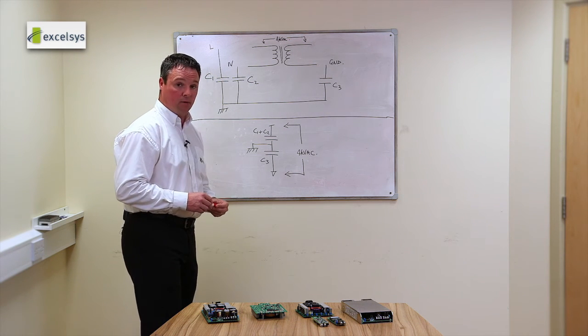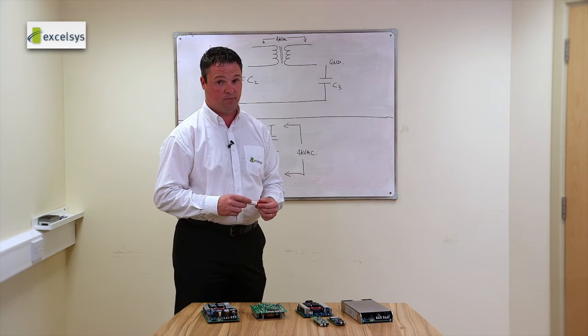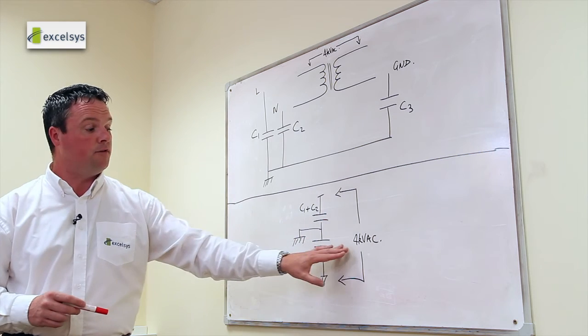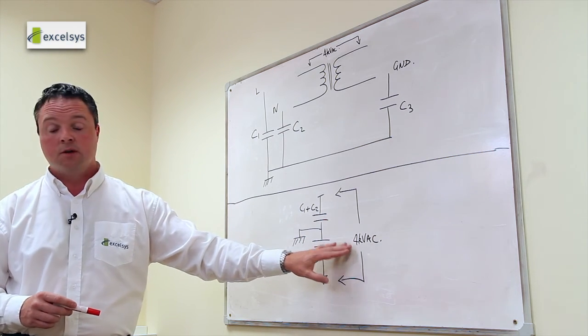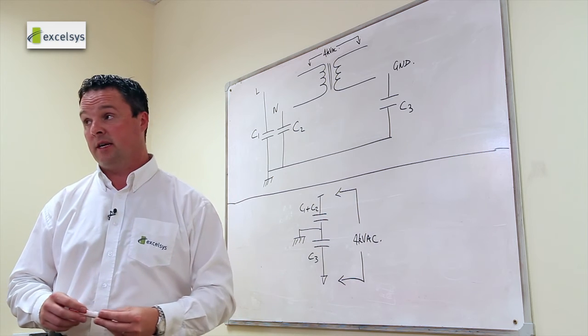And the third option, again which is permissible under sub clause 8.5.3, is that you can do a DC equivalent test of the 4kV AC. So it's root 2 times 4kV, which is approximately 5.6kV DC.